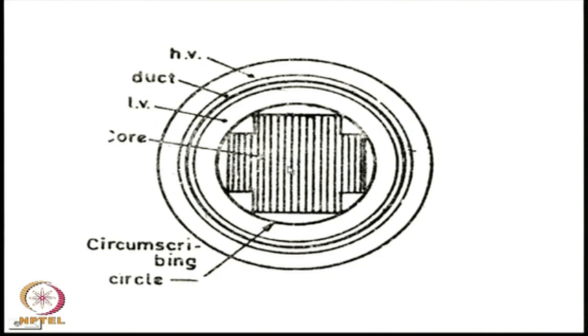One interesting thing about the core structure is that it is not square. The reason is simple. In order to support a certain amount of voltage and not to exceed a given flux density, the core cross section must have some minimum area, and it is well known that for a given area a circle has the minimum circumference. Since the windings are placed around the core, it is advantageous that this circumference is minimized, so that the length of the mean turn of both LV and HV winding can be minimized, thereby minimizing the resistance and the losses. Therefore, it is necessary to accommodate the core of a given area with minimum circumference.